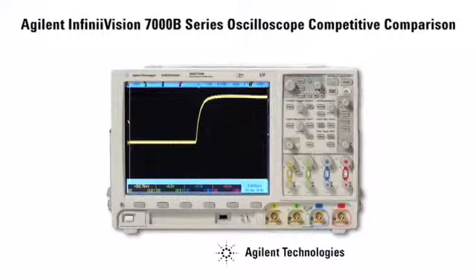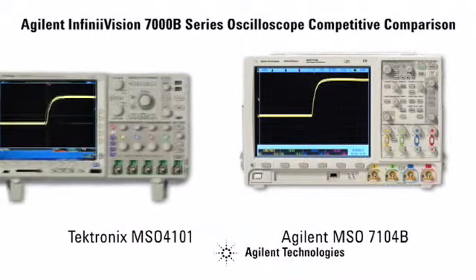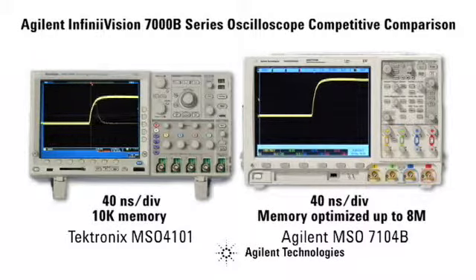As you can see, Agilent's InfiniVision MSO-7104B oscilloscope captures this glitch on average 2.5 times per second, allowing you to view elusive problems as they occur. The Tektronix MSO-4104B oscilloscope also captures the glitch regularly, as long as only the analog channels are displayed in factory default mode using only 10K points of memory.